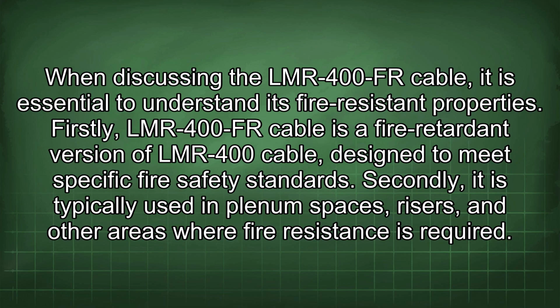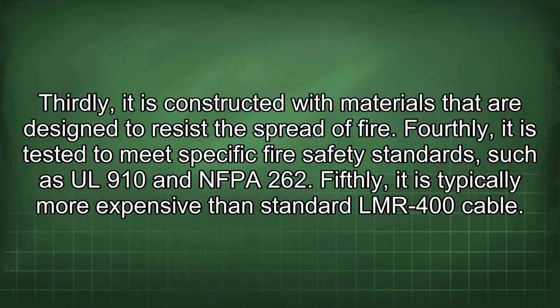Firstly, LMR-400-FR cable is a fire-retardant version of LMR-400 cable, designed to meet specific fire safety standards. Secondly, it is typically used in plenum spaces, risers, and other areas where fire resistance is required. Thirdly, it is constructed with materials that are designed to resist the spread of fire. Fourthly, it is tested to meet specific fire safety standards such as UL 910 and NFPA 262. Fifthly, it is typically more expensive than standard LMR-400 cable.